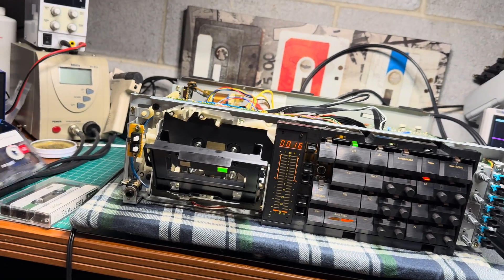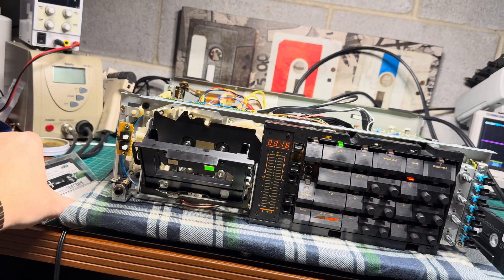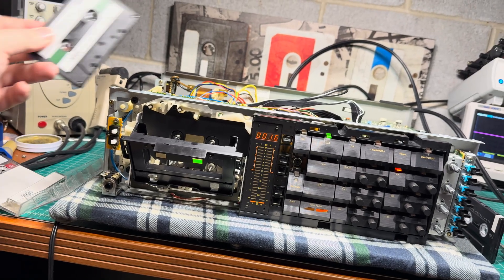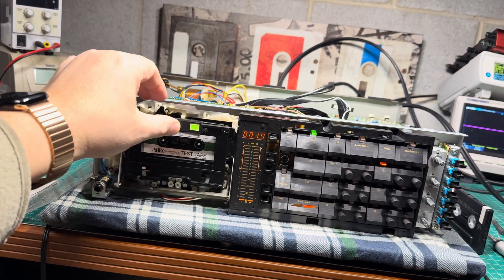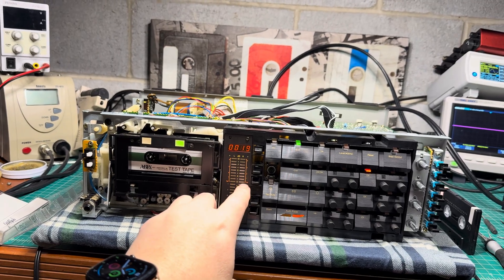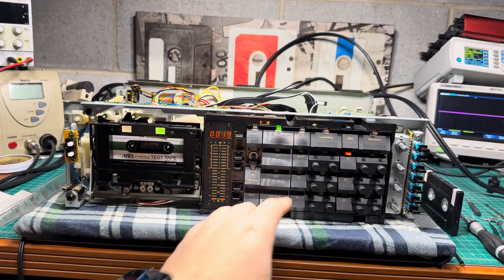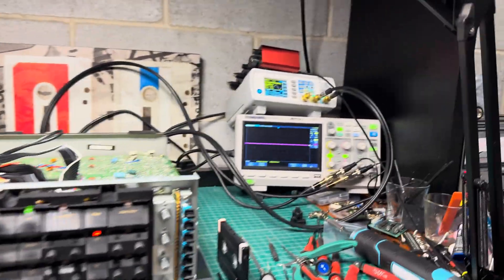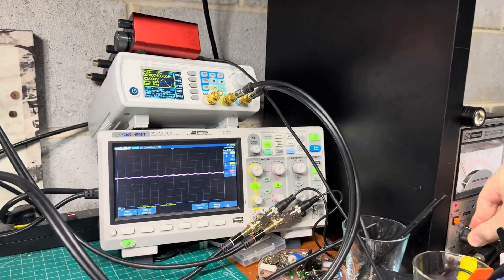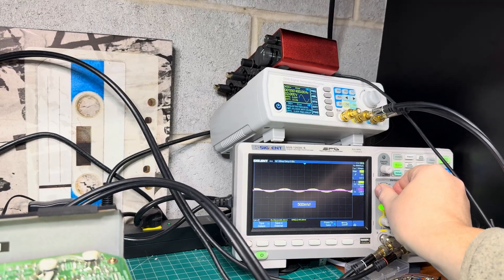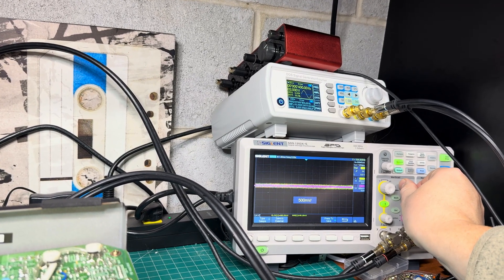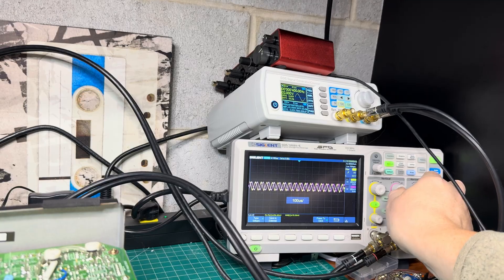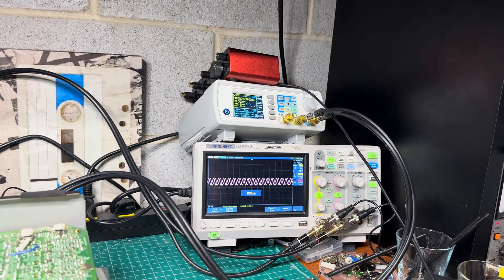I tuned levels. Levels were way off, playback levels on forward and reverse. As soon as I tuned those, the indicator started showing zeros. It's almost perfect. Now minus 20 decibel levels, it shows perfectly well amplitude. That's how the adjustment works.